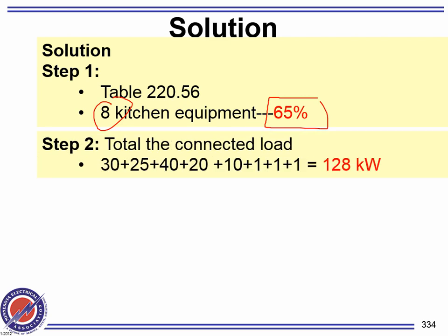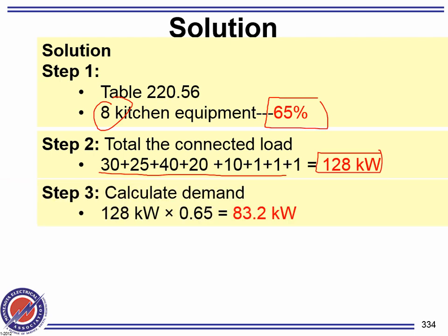Add them all up. There you go. Remember, there were 2 microwaves or something. Here's your total. Then cut them by 65, that is your demand. Can you see how it cuts it way down? Otherwise, the equipment will be huge. So that would be 83.2 kW. That's only for the equipment, gentlemen. That's only for the cooking equipment, directly related to the cooking, right?